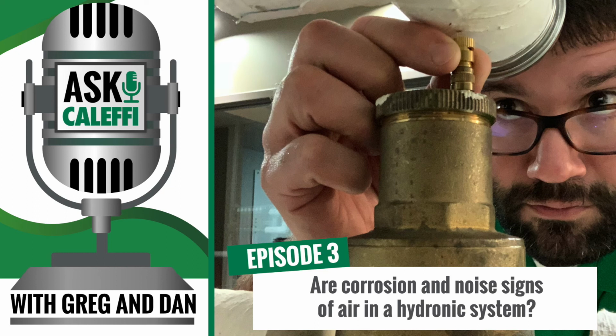Now, not to say that you can't run into problems. If there's debris in that check valve, it'd cause a leak. So in a perfect world, check valves work excellent, and honestly, they're great to have. But if you want to go one step further in your install, throw a ball valve in there. Absolutely, isolation so that you can get in and clean it out if you need to.